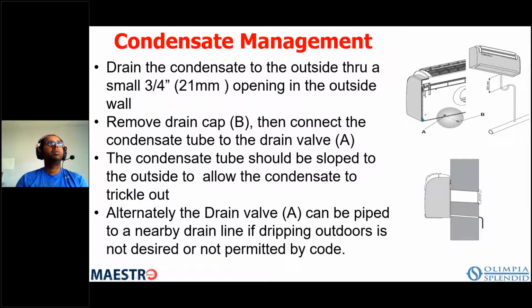So one thing to keep in mind is there is almost no condensate that comes out of this unit in the summertime, because there is a float that, when the condensate builds up enough, closes a switch that energizes a pump, and the water gets pumped up to the condenser coil, where it basically drips down on the condenser coil, provides efficiency as well as capacity gains. So most of the condensate, generally all of it, is just re-evaporated and goes out through the air as a vapor. So there's nothing to drip outside in the summertime.